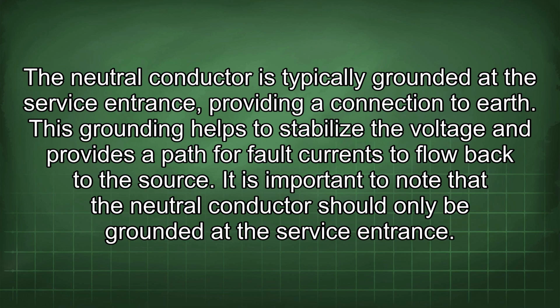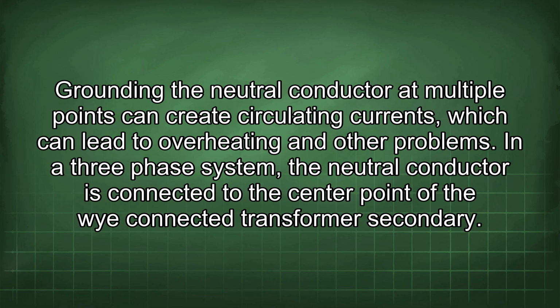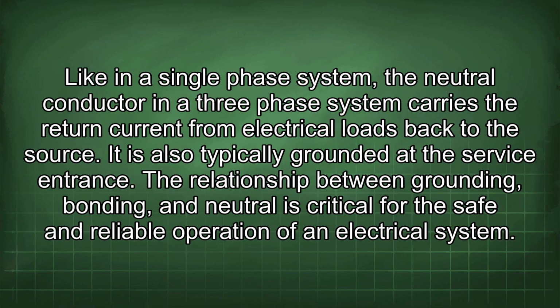It is important to note that the neutral conductor should only be grounded at the service entrance. Grounding the neutral conductor at multiple points can create circulating currents, which can lead to overheating and other problems. In a three-phase system, the neutral conductor is connected to the center point of the Y-connected transformer secondary. Like in a single-phase system, the neutral conductor in a three-phase system carries the return current from electrical loads back to the source. It is also typically grounded at the service entrance.